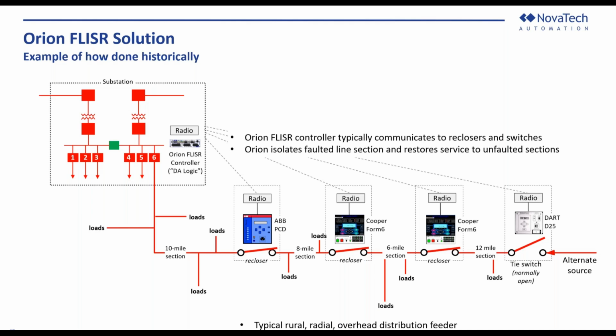In this example, how we've done historically, this distribution line spans over 36 miles through a rural area, featuring overhead distribution feeders. At the substation, we have a FLISR controller with the DA logic, which acts as a major FLISR controller that's talking over radio to various different vendors, reclosers, and switches. The idea here is Orion will isolate the faulted line section and restore service to the unfaulted section.